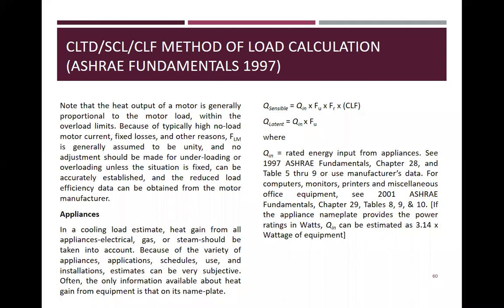Okay, appliances. In cooling load estimate, the heat gain from all appliances, electrical, gas, or steam should be taken into account. Because of the variety of appliances, applications, schedule, use, and installation, estimates can be very subjective. Often, the only information available about heat gain from the equipment is that on its nameplate.